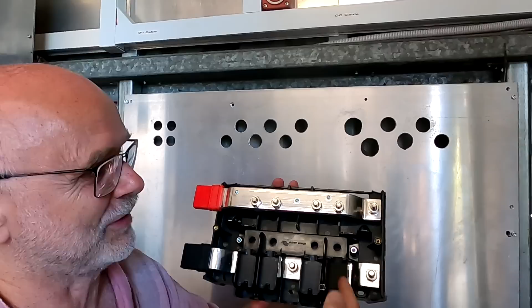So pretty much a similar setup as we have here, where we have a shunt which measures the energy going in and out of the battery, a main breaker, and a DC bus system where solar charge controllers and inverters connect to. I found this 1000 amp bus bar online, which comes with all the connections and a nice cover. The whole bus bar sits in a case already. We don't need to design or build anything. It is already nice looking and very compact.